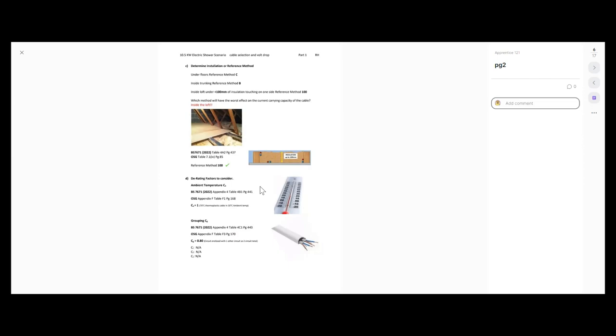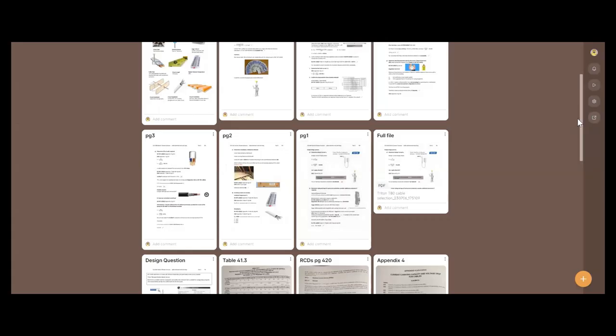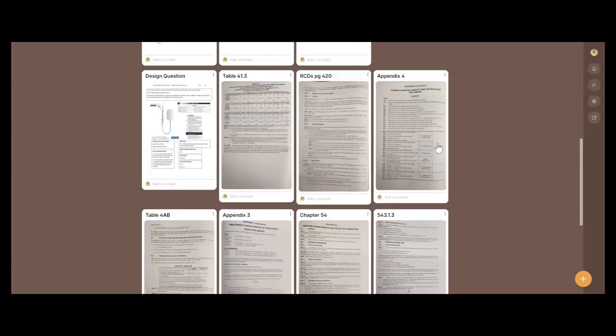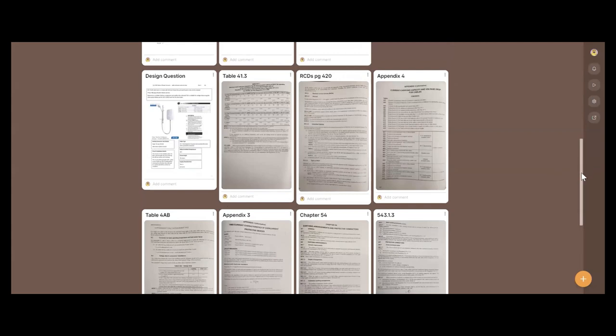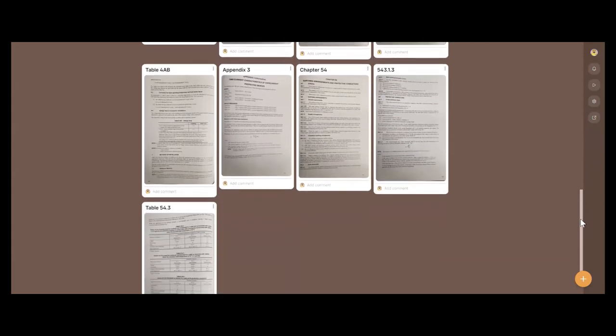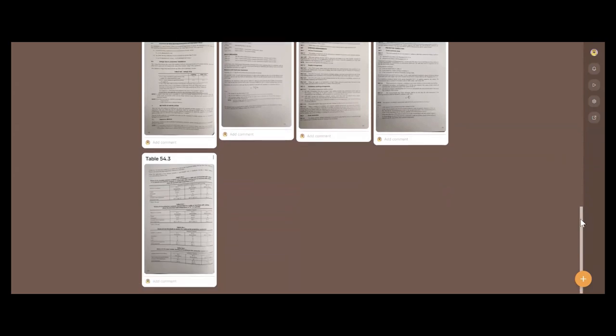What derating factors have we got to consider? We've got an ambient temperature of 30 degrees maximum. I need to go to table 4B1 in Appendix 4 of the regs on page 441, or in the on-site guide it's page 168, Appendix F. The column on the left looks at ambient temperature. I select 30 degrees and go across to 70 degree thermoplastic, and it gives us a rating factor of one. So no derating required — 30 degrees is the normal expected ambient temperature anyway.